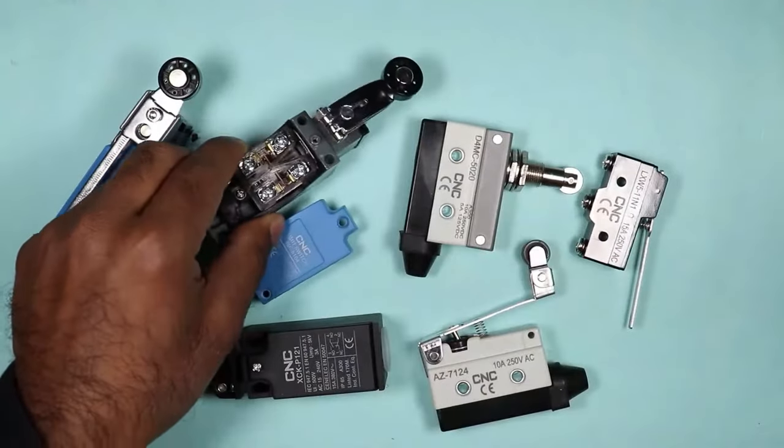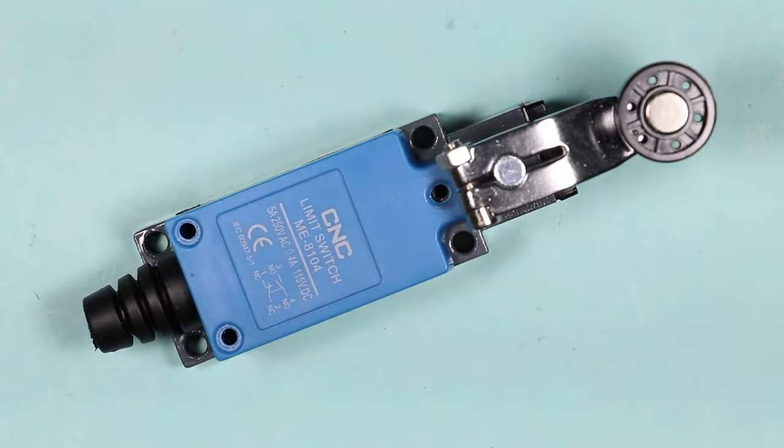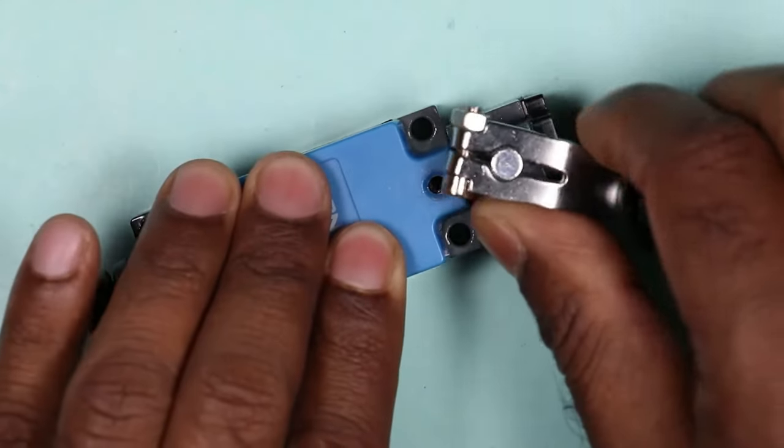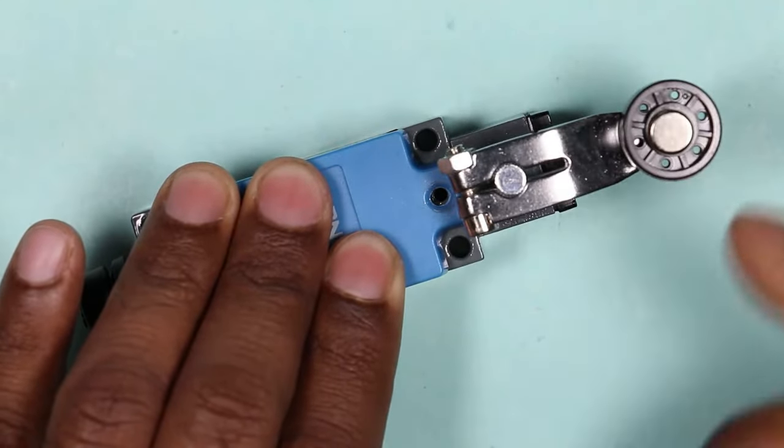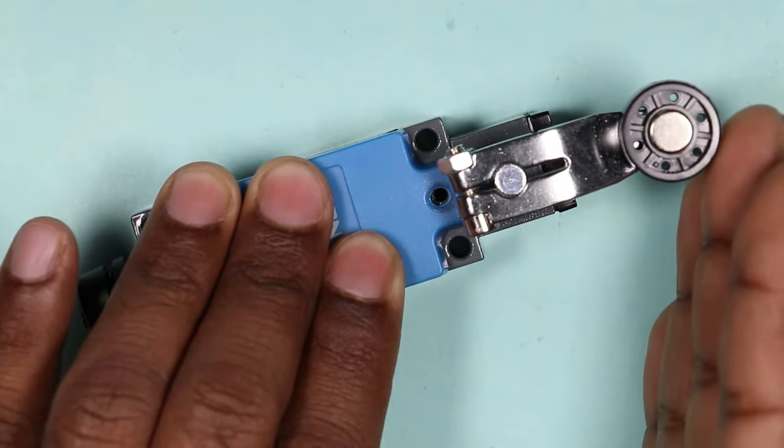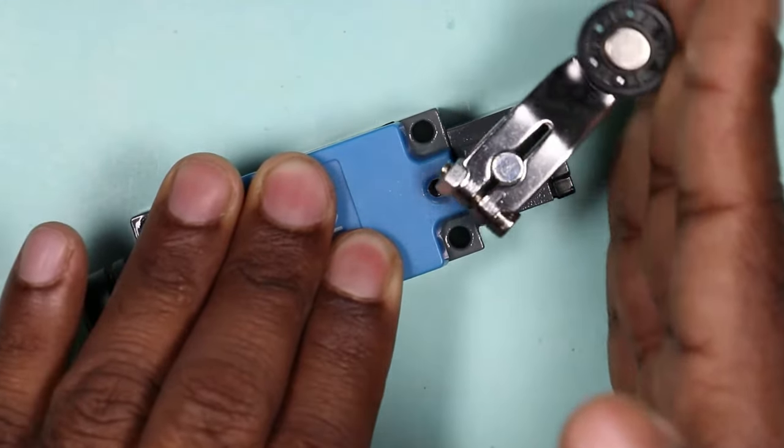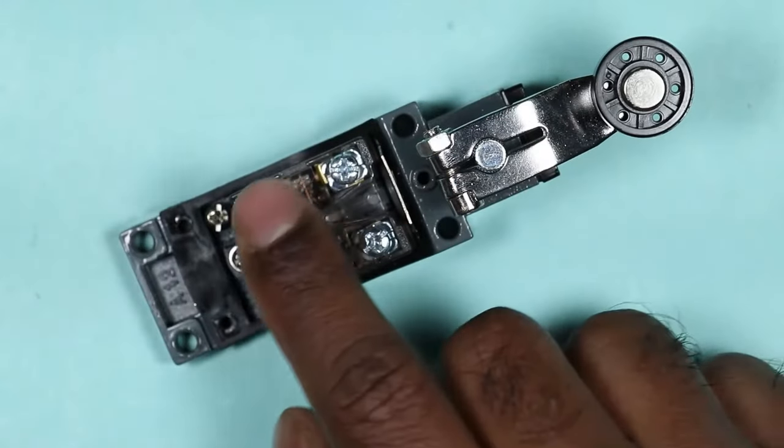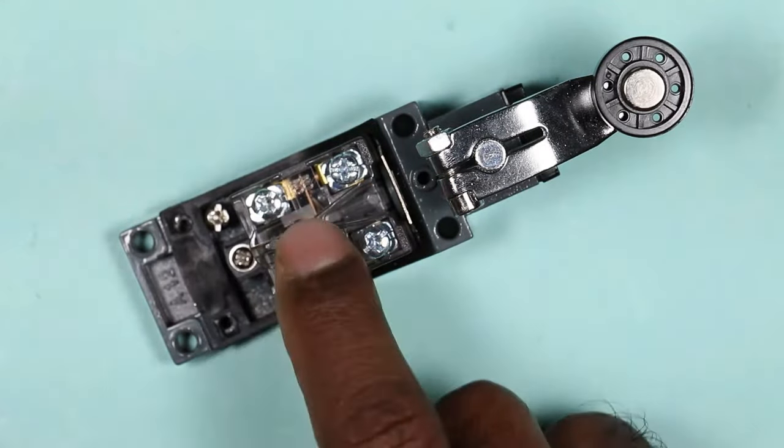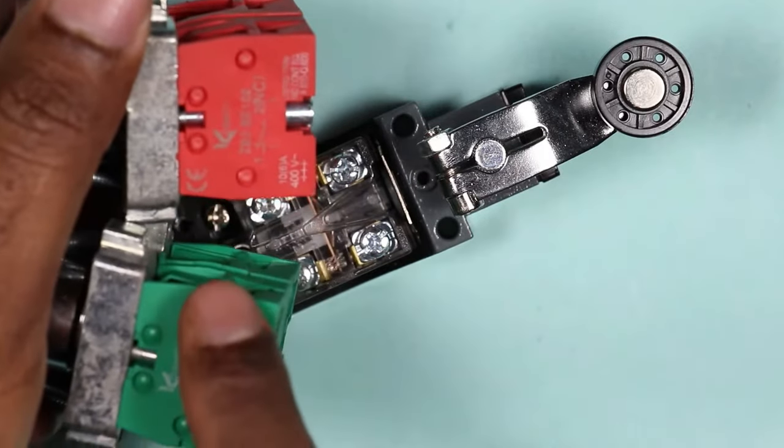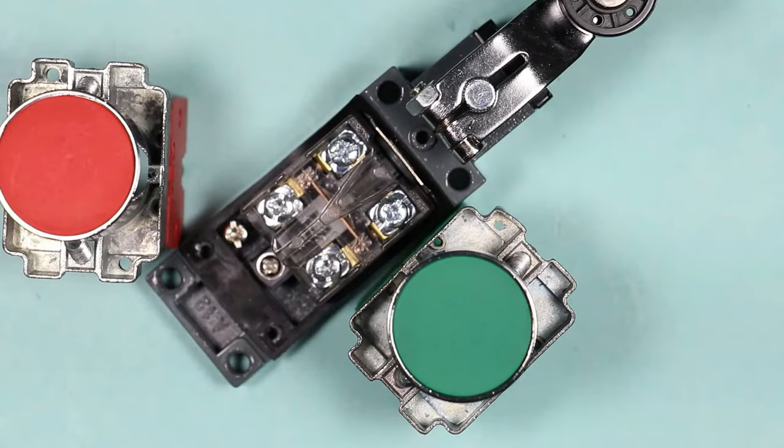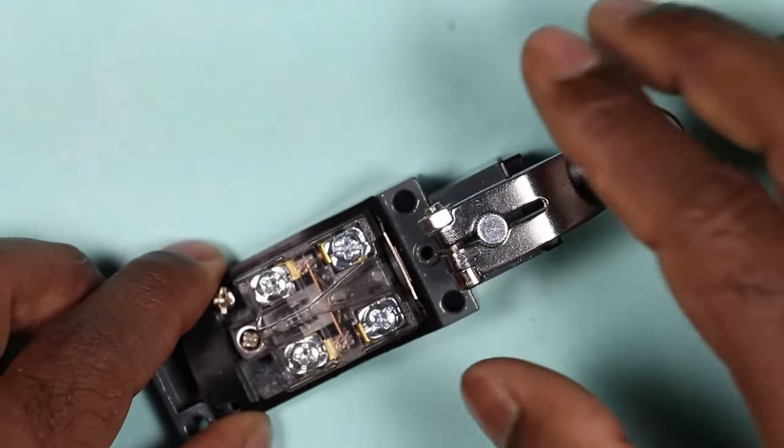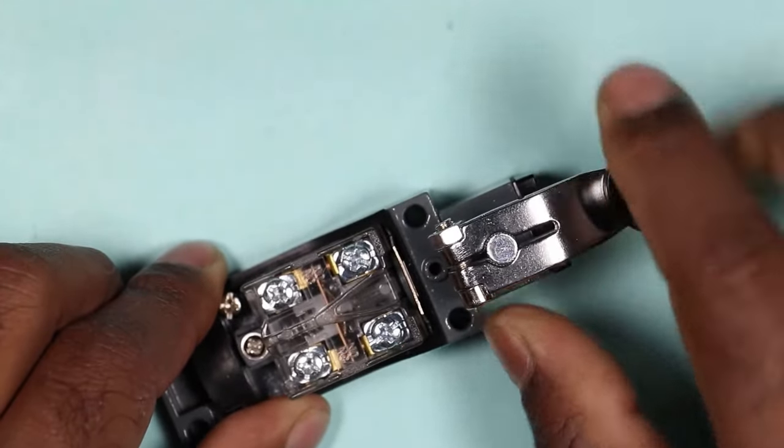Before moving to wiring part, let's understand some basic knowledge of this limit switch. This part in limit switch is known as plunger. On top of plunger, roller is given. This roller contacts with moving part and plunger gets operated. When this plunger operates, then inside the switch, an element is present, which is exactly like NO and NC contact. The way in which push button changes NO and NC contact, in the same way limit switch changes NO and NC contact by movement of plunger.